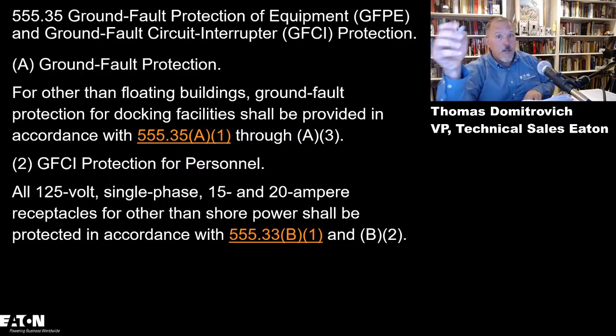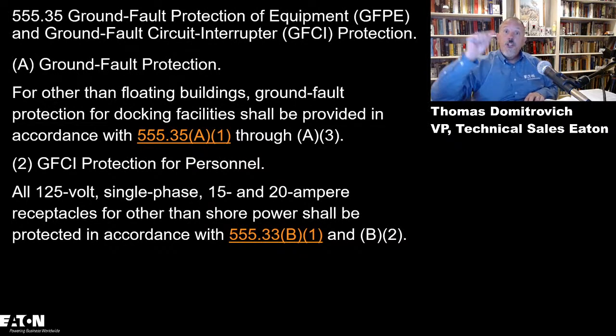So that was another part of the effort in the 2020 cycle, moving things and pointing things back to 210.8, because we want to make sure that we align ourselves with 210.8 and those requirements for those outside circuits and etc. Right? And then B1, B2 says receptacles other than those supplying shore power, because remember, shore power is going to be at 30 milliamps. And it says, other than those supplying shore power to boats shall be permitted to be enclosed in marina power outlets with receptacles that provide shore power to boats, provided the receptacles are marked to clearly indicate that the receptacles are not to be used for shore power.